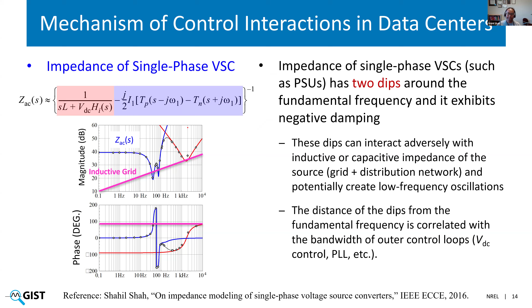Because they saw these oscillations around the 2018, 2019 timeframe within the data centers, the outcome of the analysis was that some of the IT racks were interacting with the power supply, which was basically the data center building, right from the grid POI through all the transformers up to the terminal of the IT rack. They came up with this term, building impedance ratio, or maybe it's base impedance ratio. This is very similar to the short circuit ratio that we use in power system studies.